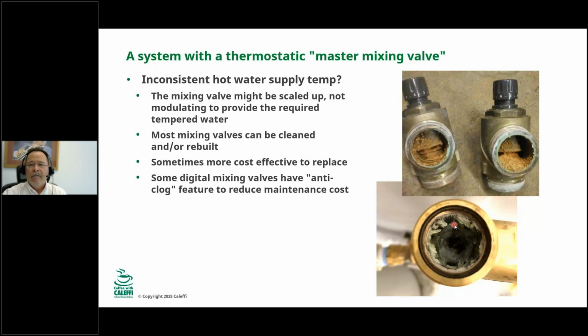So, if you've got a building where this is critical, you might have a backup one ready to go and just switch out the union nuts and then take the one that's plugged up and just soak it overnight in a descaler, and then you always have a quick couple-minute fix for that instead of having to take it out, have the building shut off for a period of time until you can service it. But yeah, it's really hard to make this go away.